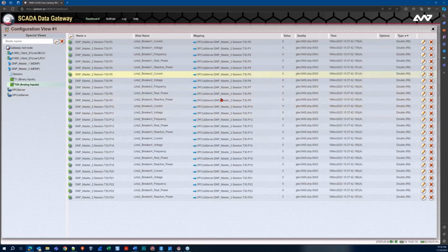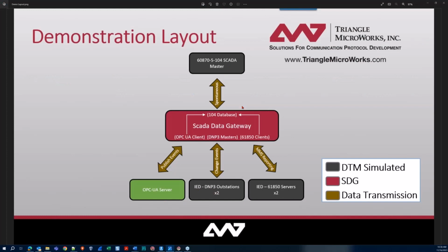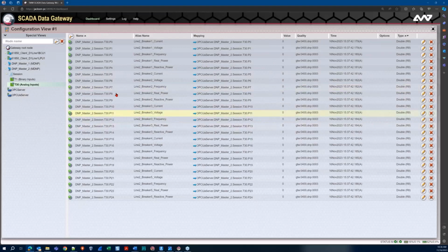All right, so we're still not quite ready to begin passing data up to my 104 master. I still need to bring in data from my OPC UA server. So just a quick word before I start doing that. Everything we have brought in thus far into Gateway has been brought into an internal OPC UA server, which is what you see here. The mapping is really done automatically. So if I did have a local HMI or something like that that needed to read data from my gateway via OPC, that work has already been done.